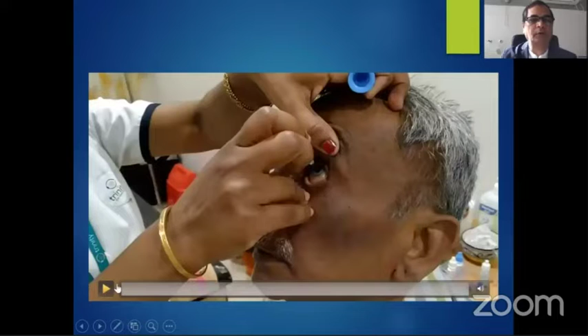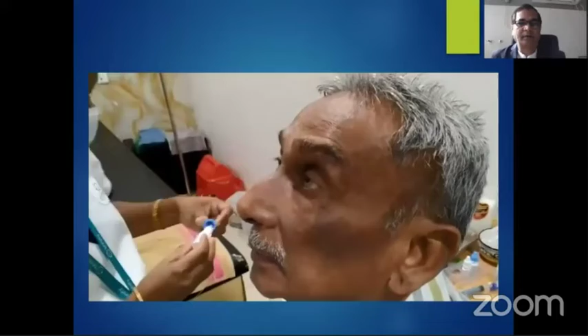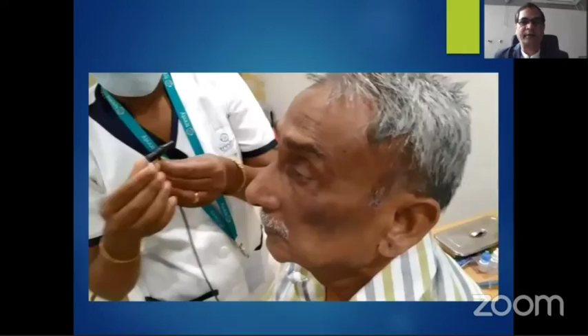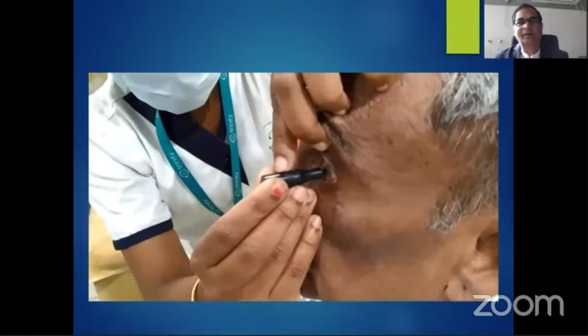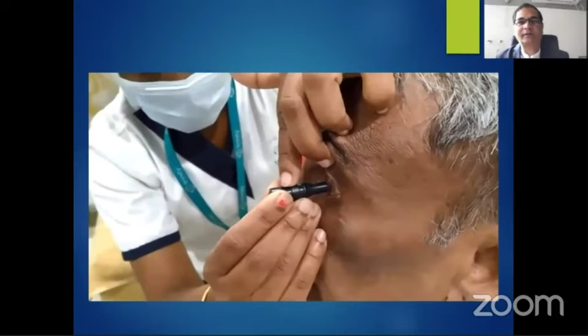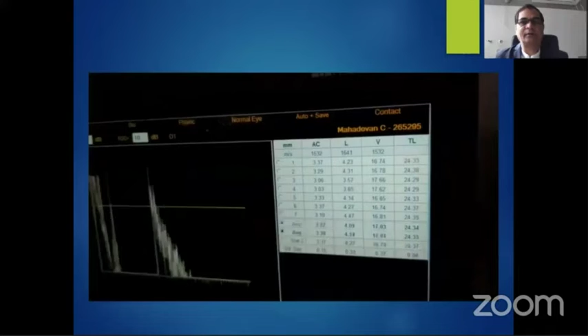And this is the photographic presentation of the same. In this video, I'm just going to show how to do the application. This is instilling of anesthetic eye drops. The patient's head should be in proper position, and you have to ask the patient to look straight at a fixation target, and then open the eyes, keep the head straight, bring the probe, stabilize the probe with the other hand, and just touch the apex of the cornea. And once it is aligned properly, the machine will automatically start taking the reading. This is the automatic mode.